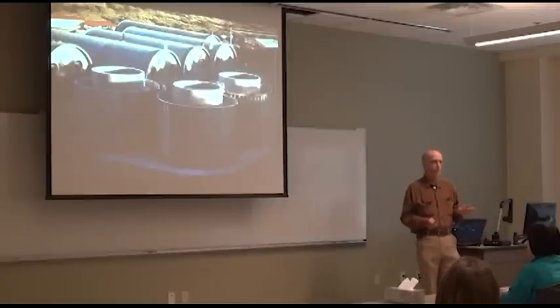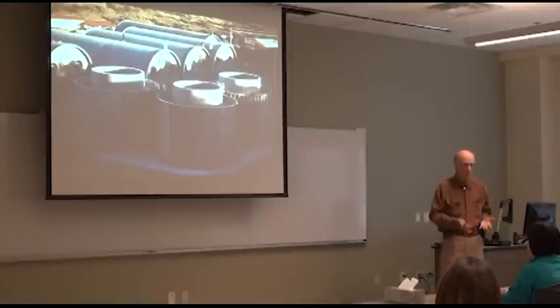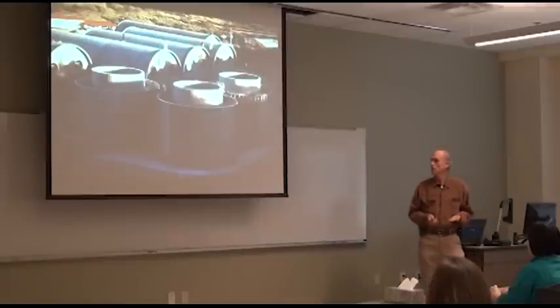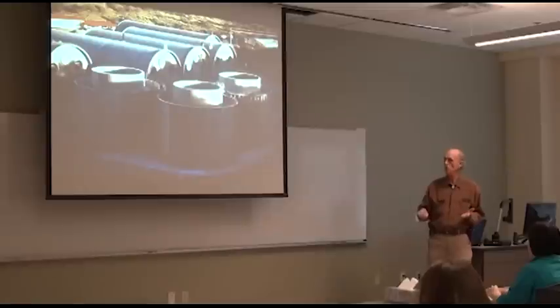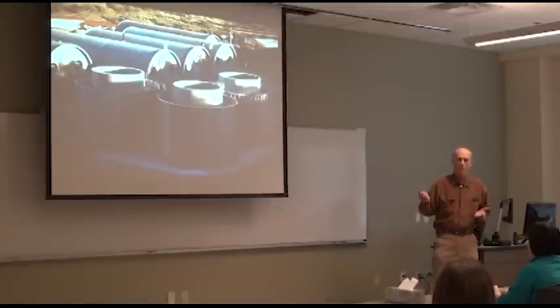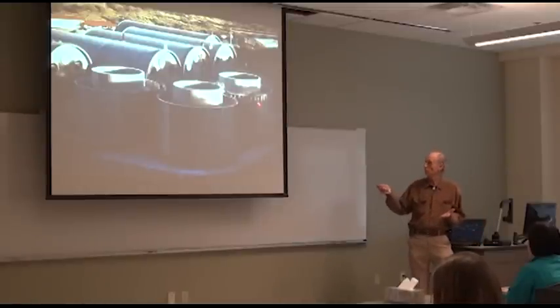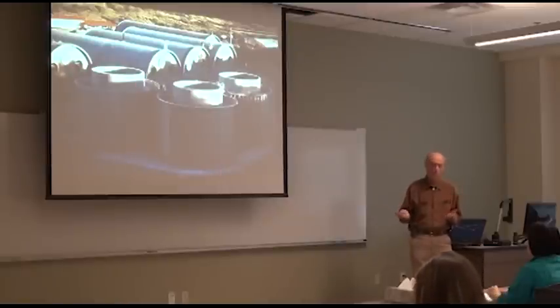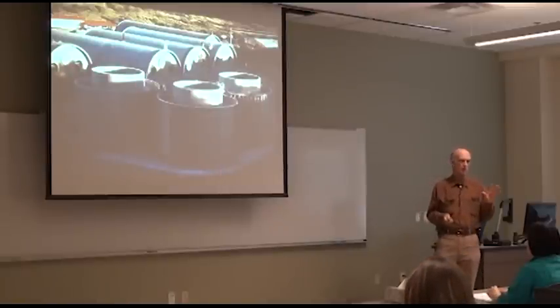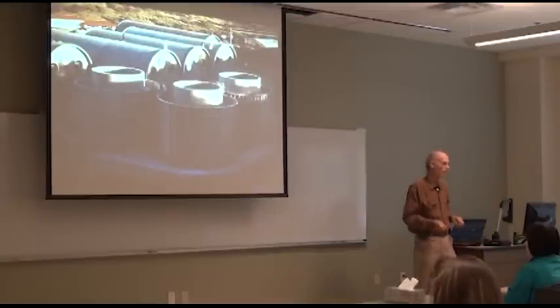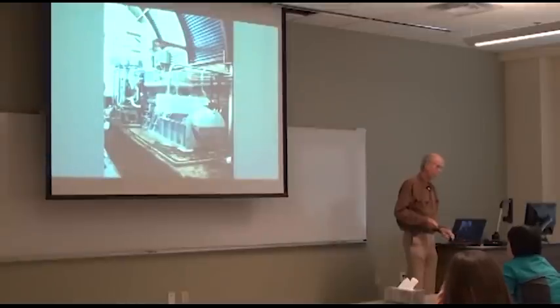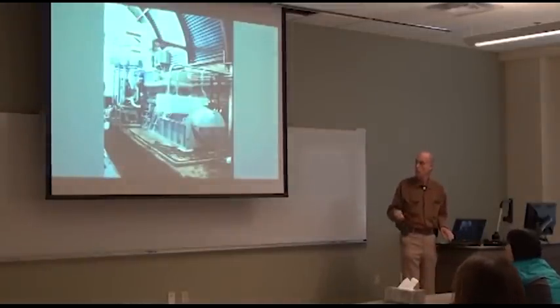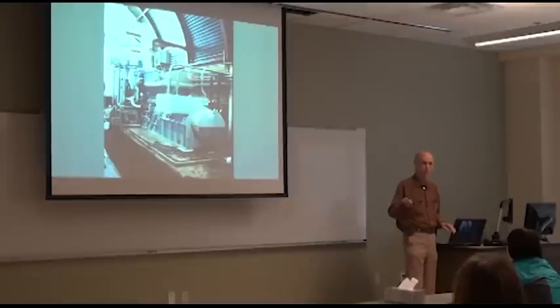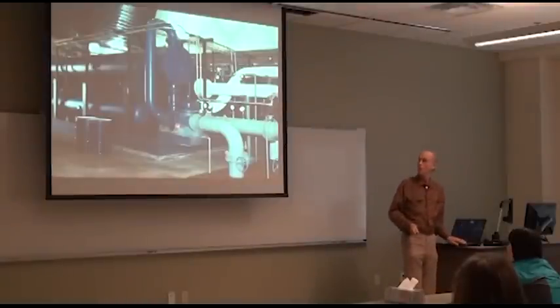The main way that you dissipate heat, which of course was pouring into Biosphere 2 by sunlight, but also heat that was necessary because of the operation of the electric generators, was the main way that one does that economically is to evaporate water. On a hot summer day, we were evaporating about 200,000 gallons of water a day. And here's one of the 1.5 megawatt generators. We used waste heat from that to operate an absorption chiller, by the way. And here are the ammonia chillers.